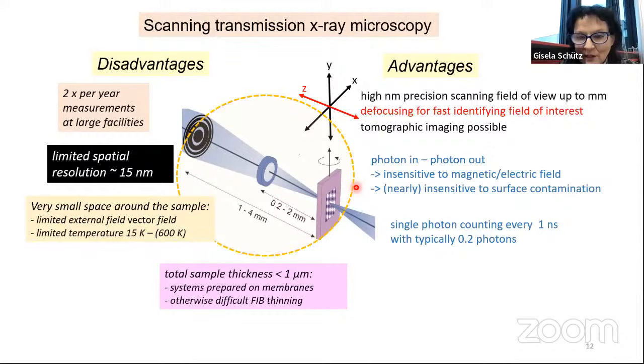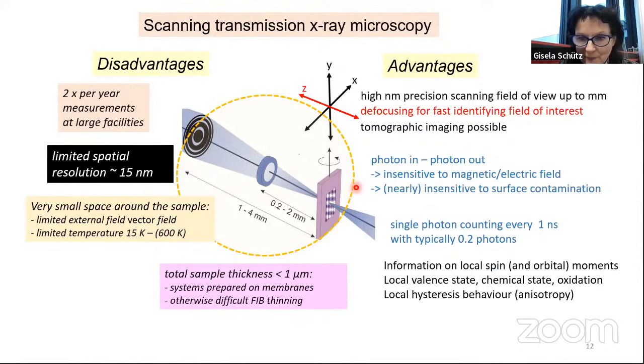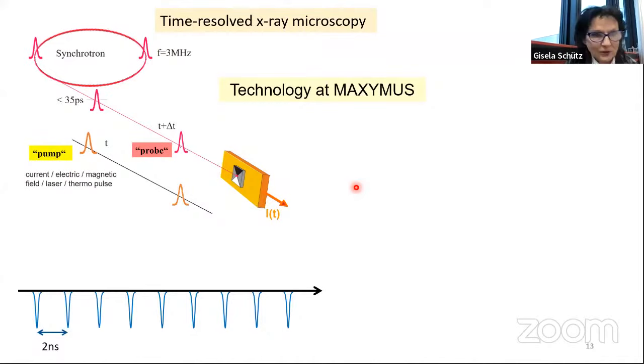But what is the advantage? You have high-precision scanning. You can also turn the sample for tomographic measurements. Then you can move here the sample in set direction, so you can easily defocus and find quickly the field of interest. So tomographic imaging is possible. Photon in, photon out, means you are insensitive to magnetic or electric fields. And you are nearly insensitive to any surface contamination, which you have for beam or electron microscopy things. So you have, with the photon avalanche diode, you can single photon counting every one nanosecond, and you can use all the benefit of XMCD and XMLD.